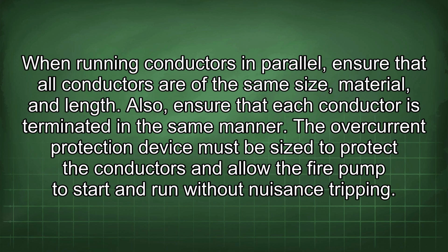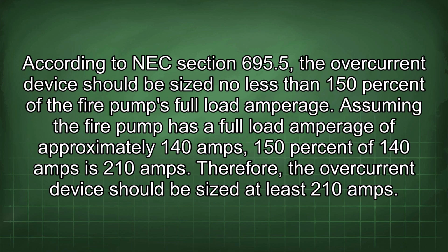without nuisance tripping. According to NEC section 695.5, the overcurrent device should be sized no less than 150% of the fire pump's full load amperage. Assuming the fire pump has a full load amperage of approximately 140 amps, 150% of 140 amps is 210 amps. Therefore, the overcurrent device should be sized at least 210 amps.